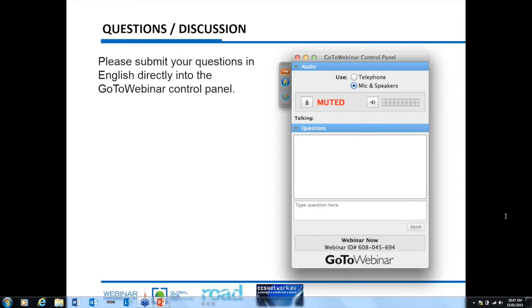All right, thank you. Do you see any corrosion issues because you're using direct seawater cooling? And what materials have you used to construct the heat exchangers that are exposed to that seawater? I think they're all titanium, is that right? Yeah, I'm getting a nod from Heather. They're all titanium heat exchangers. It's the same basic design as the heat exchangers in the main power plant condenser.